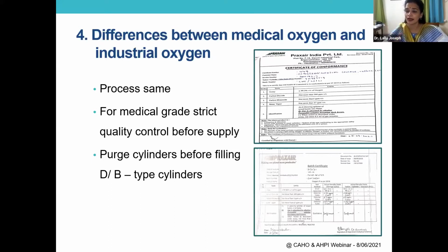Anytime the LMO tanker leaves the manufacturing facility, it needs to have a quality check done for every supply that goes out. You need the QC certification, and that certificate has to be handed over to the hospital, showing the stringent QC that goes with medical grade oxygen, which is not so with industrial grade oxygen.